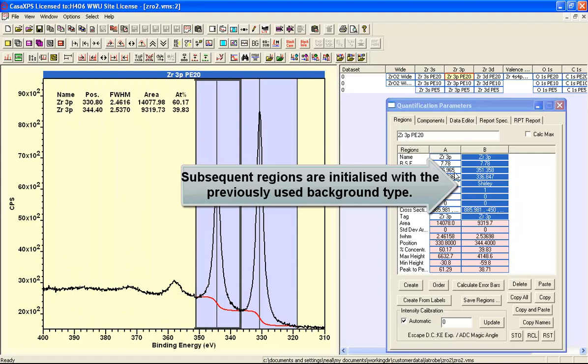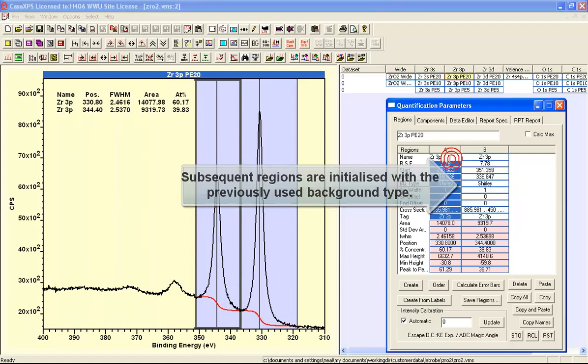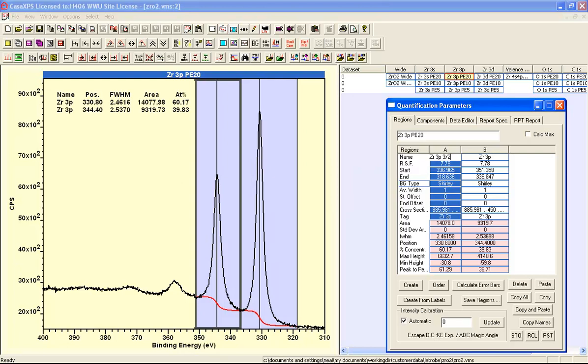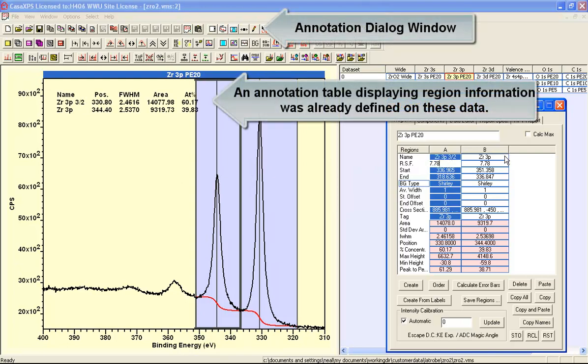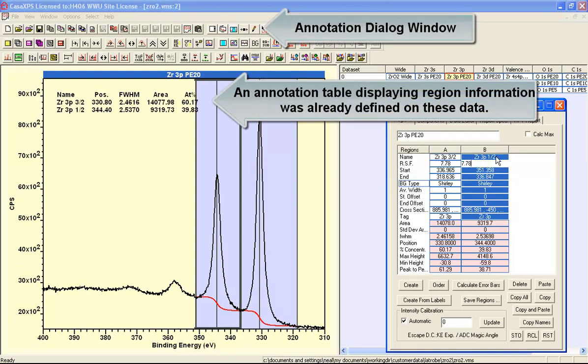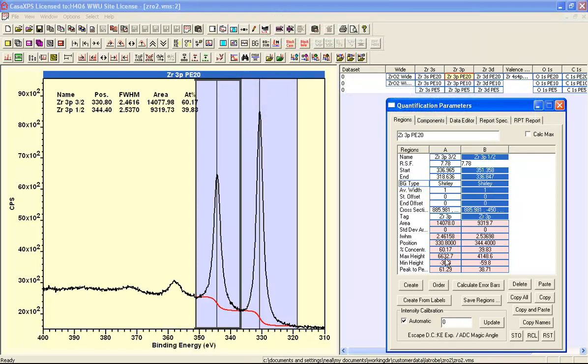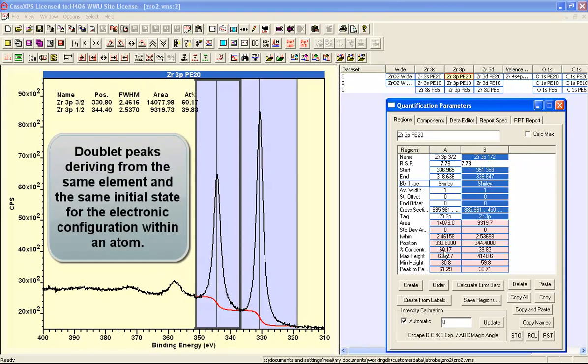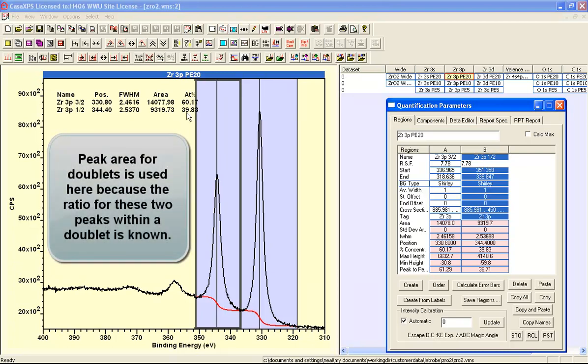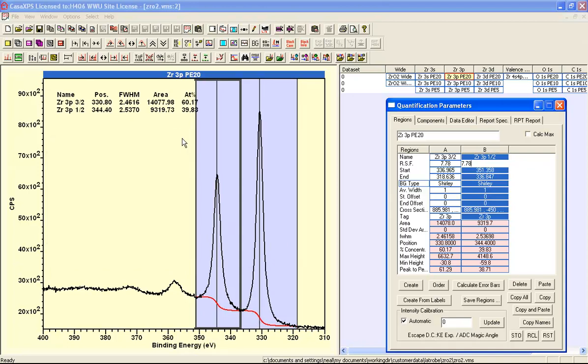So I've got two peaks, one representing the 3 halves and one representing the 1 half peak in this doublet. The ratio that we ought to get for these peaks should be 2 to 1, so we'd expect the area as a percentage to be 66.66 to 33.33. We can see that if we use this Shirley background, we're not getting the expected ratio for this doublet pair.